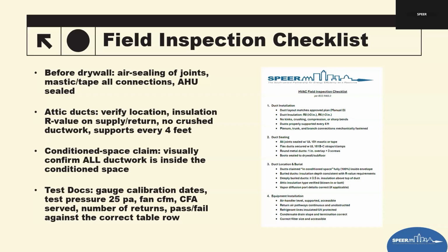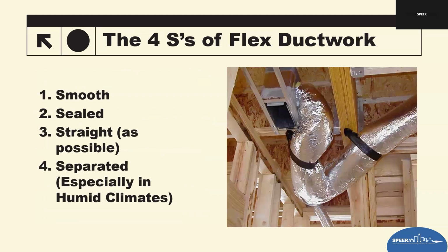Thank you. And then a surprising number of test reports could possibly fail because they're using the wrong row on the table. So this checklist will help ensure that field inspectors align the design documents and duct leakage test results. Hopefully most of your building officials now have electronic documents that they can view in the field. This is going to be helpful when you walk the site and want to check whether they are installing what they're claiming, and that the testing results listed on the compliance form are adequate. Catching problems early, of course, prevents failed final inspections and saves everyone time and money. So I'll include this checklist in the email.